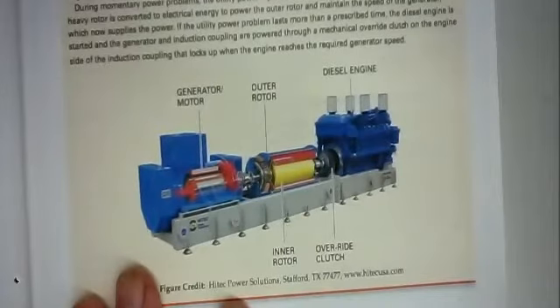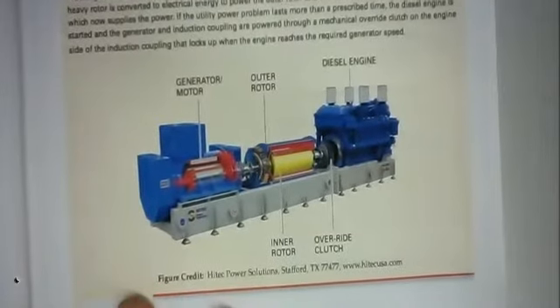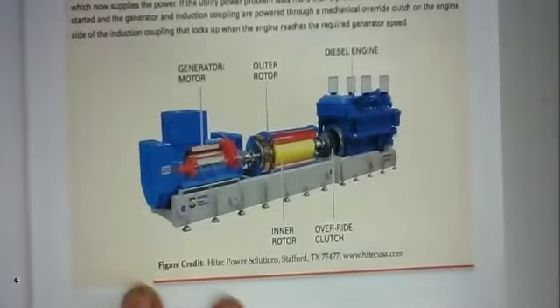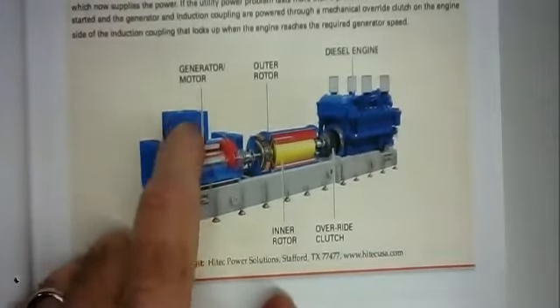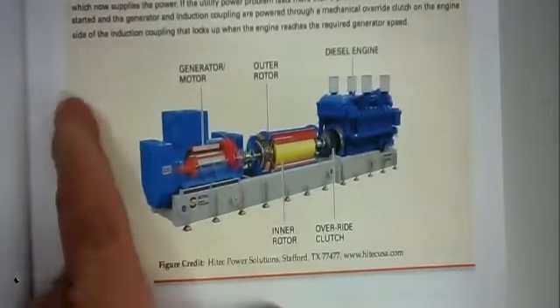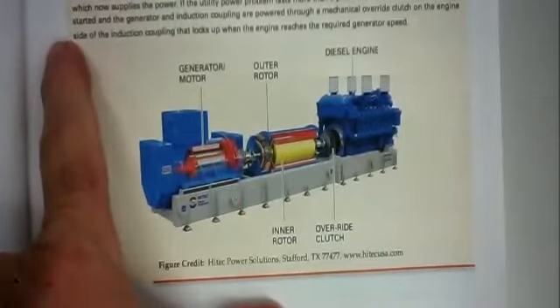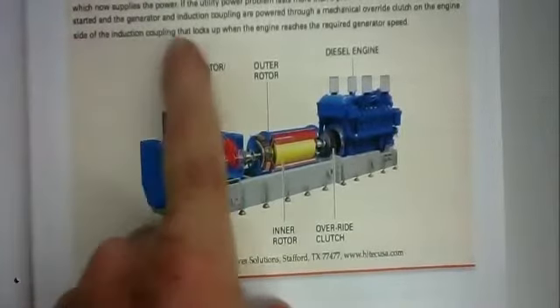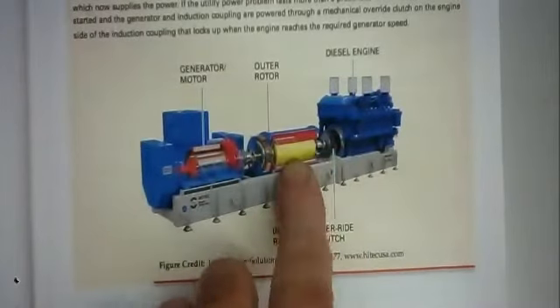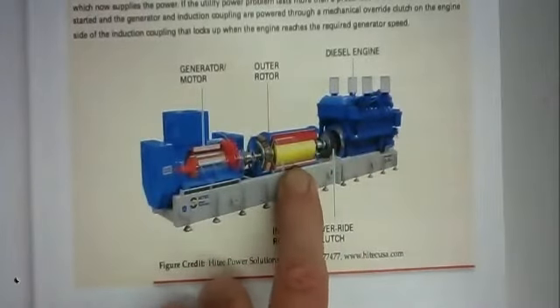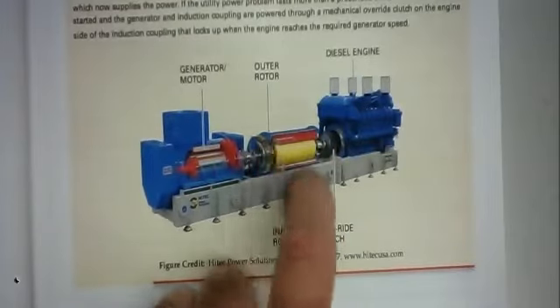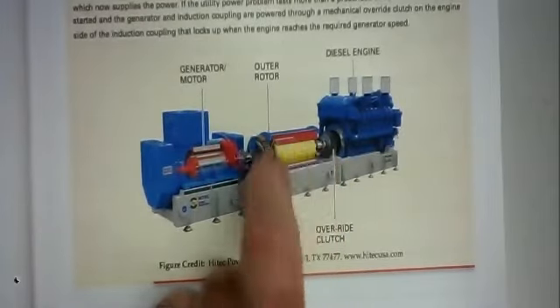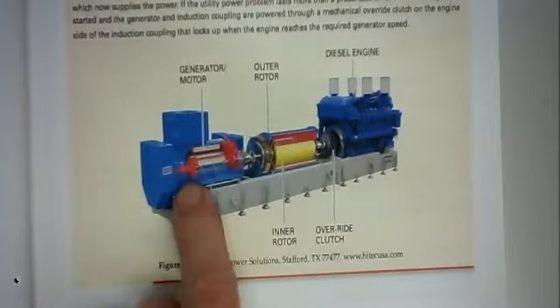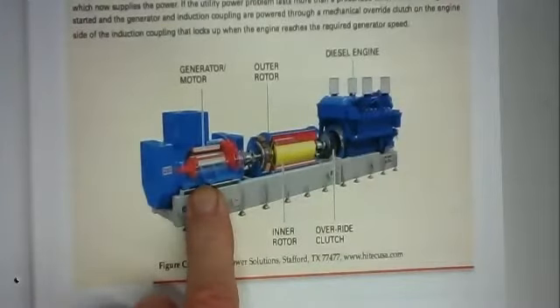It's a generator, motor generator set. When you have electric power coming from the utility, you have an electric motor that spins this rotor. This rotor is probably 4,000 pounds. Once you get it spinning, inertia will keep it spinning. And it's turning this generator, and the generator is generating power.